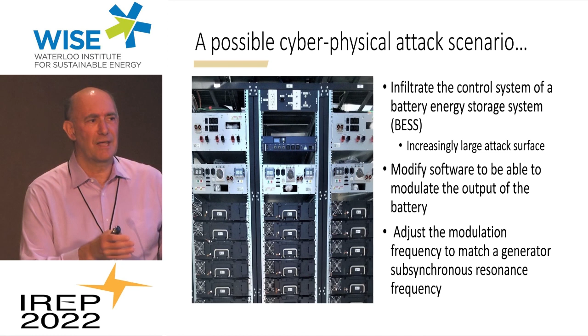So I thought I would give you a little refresher on that. In a turbo generator, you have the low pressure, medium pressure, high pressure, the generator, and the exciter, all on one shaft. Those are big masses on the shaft, which can be modeled as a spring, so you have a spring mass system.